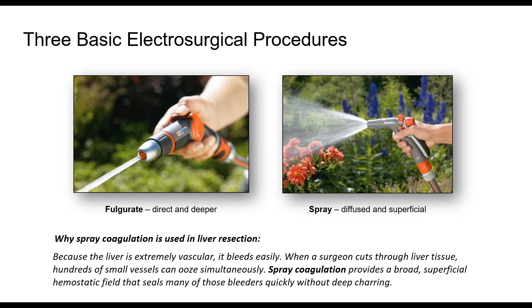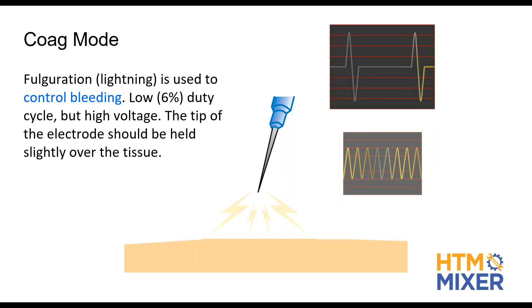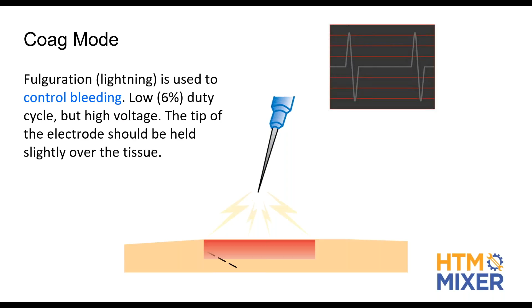All right, coag mode. As you can see in this waveform here, it's going bang, cool, cool, cool, cool, bang, cool, cool, cool, cool, bang. So 6% of the time, that thing is hitting. That's the way it's designed to do. If we compare that waveform to the cut waveform, you can see how different they are, and the effect on the tissue changes as well. If you hold the pencil up off of the tissue, whoever created this calls it fulguration, but actually it's spray, because they're holding that thing so far up off the tissue. But it's just an illustration anyway. So it's going to find that path of least resistance.